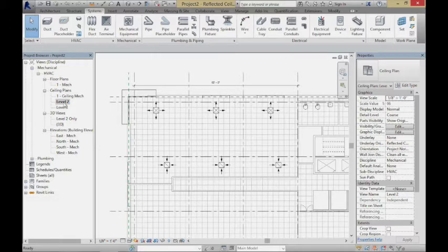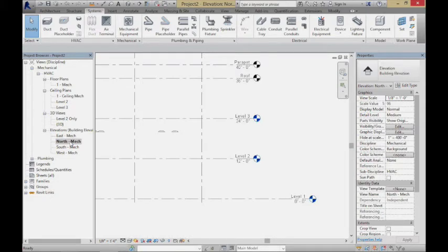So I put these at 8 feet. I have 12 feet to go there, so I actually have about 4 feet to work with, less the floor, less the structural, stuff like that. I still want to keep it fairly tight in here. So I'm going to decide, as I'm running these, to put the returns below the supplies. I'm going to give them a little bit of vertical differentiation so they can pass each other if they need to.